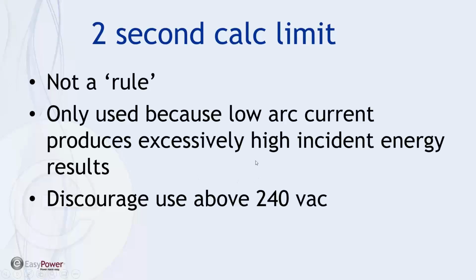Let's go back to my presentation. The fact is, we used to say the 2 second rule is not a rule because it was in the annex. Now it's been moved to the body of the standard. So, okay, let's admit it's a rule. In the standard, they imply that the 2 second limit can be applied across all voltages. I would discourage the use of the 2 second rule above 240 volts because in the 480 volt range, you're talking not only potential for obscuring the coordination issue, but actually having results that could hurt people that were slow getting out of the way. So that's the 2 second rule.